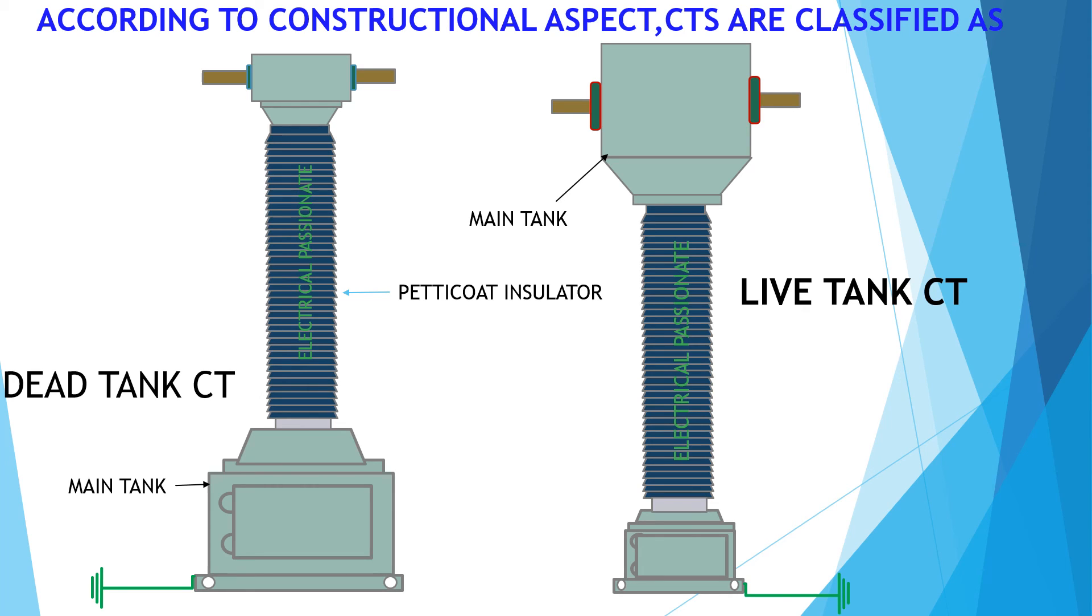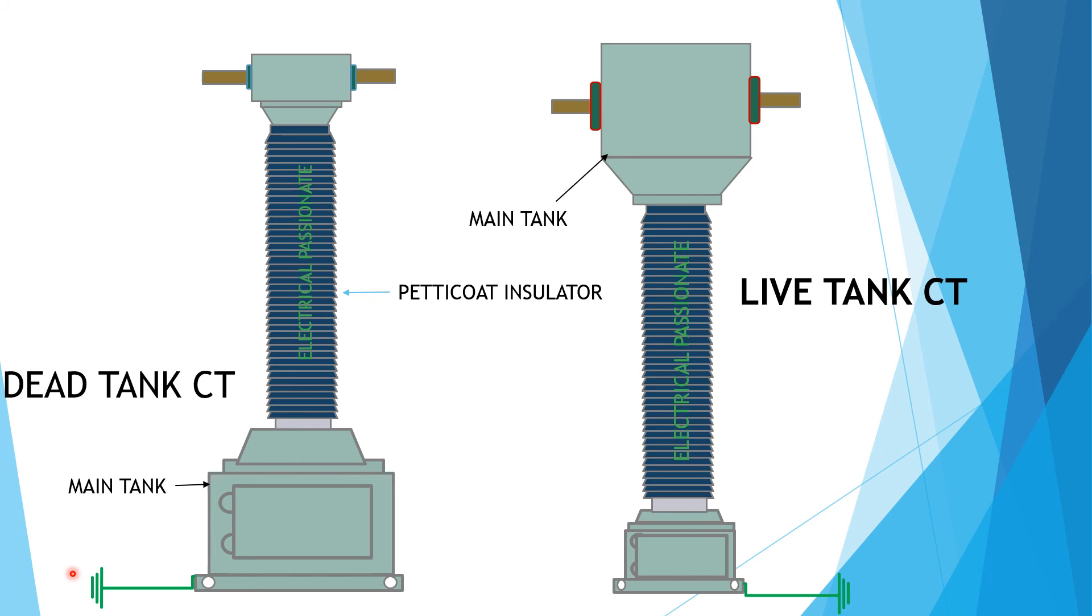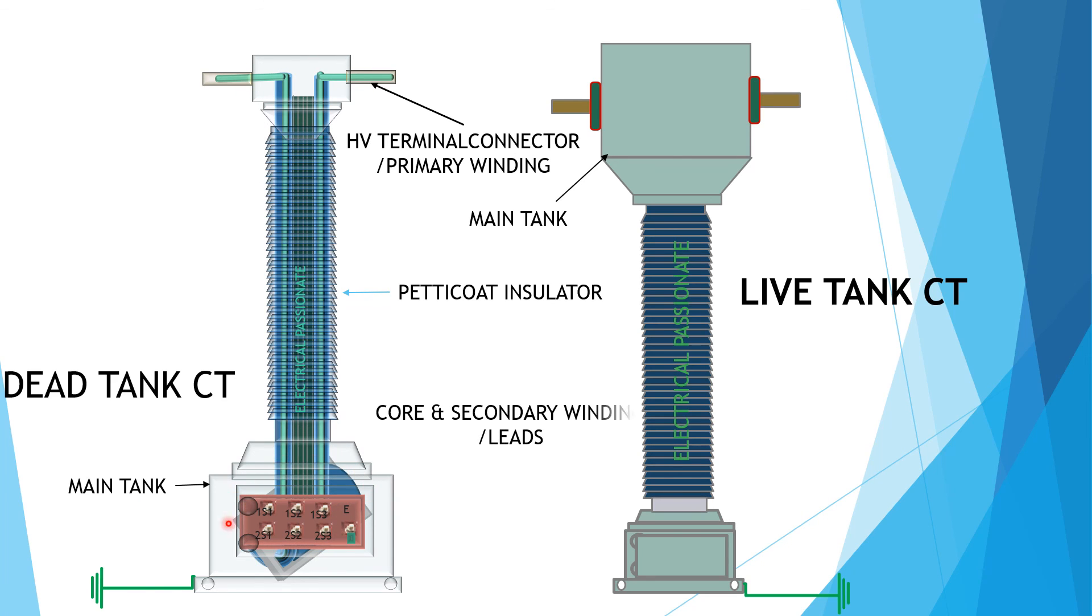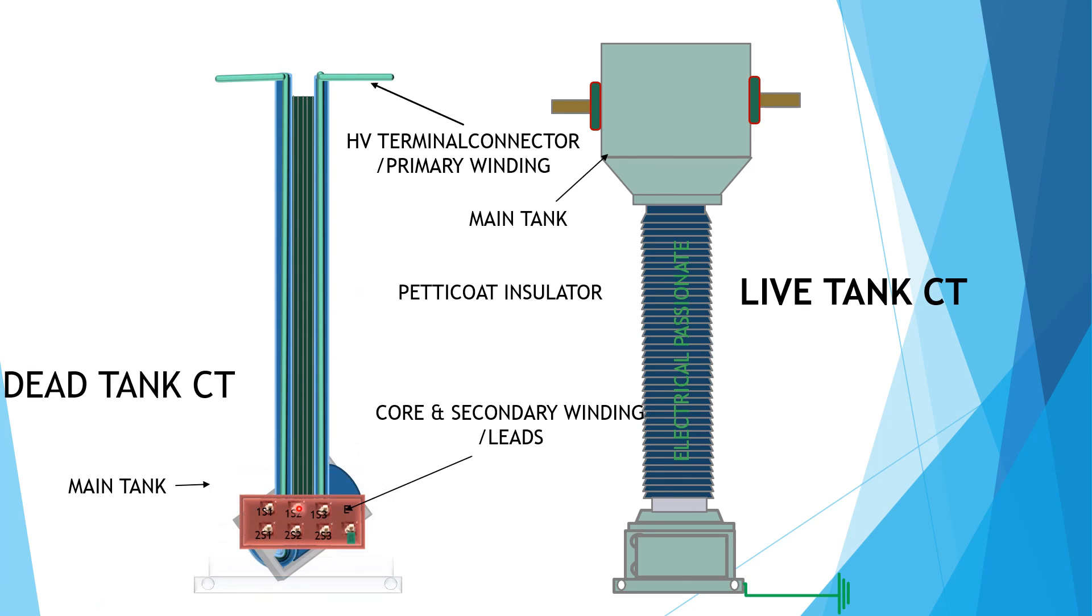If core and secondary windings of a CT are located at a tank insulated from earth potential, is called live tank CT. These are dead tank CT. Here core and secondary windings are located at this tank. The tanks are kept at earth potential. Primary HV terminals are insulated from the main tank by suitable insulated petticoat. Insulated primary winding is drawn at here.